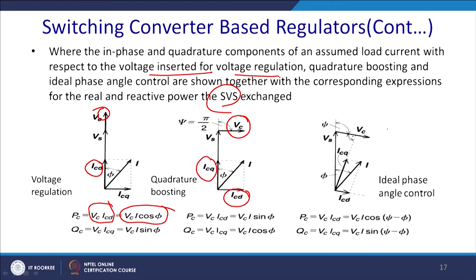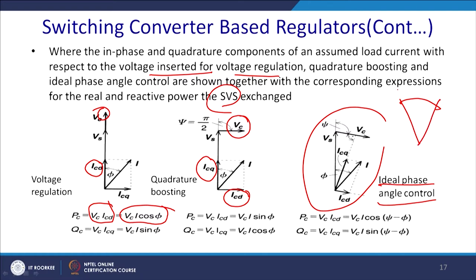But in ideal angle control, what you can do is inject VC with any angle phi, and in that way you can compensate real power as well as reactive power. So this is the ideal phase angle control, because you have to inject current into it. So this one is V1, this one is V2, and this one is phi. So you have to inject in this way, not in quadrature or in phase.